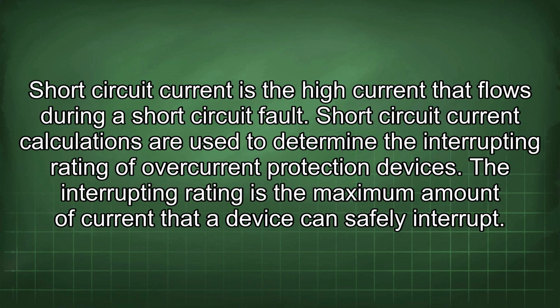Short circuit current is the high current that flows during a short circuit fault. Short circuit current calculations are used to determine the interrupting rating of overcurrent protection devices. The interrupting rating is the maximum amount of current that a device can safely interrupt.